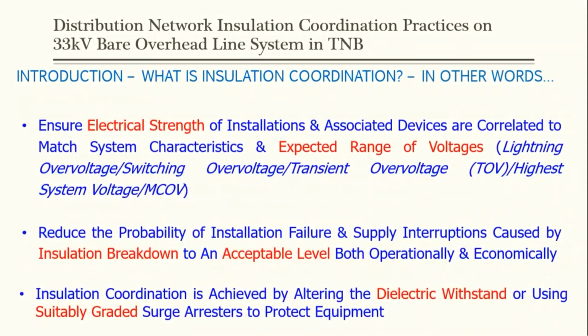So in other words, because we have a mouthful of definitions from IEEE and IEC, to put it simply, we want to ensure the electrical strength of insulations and associated devices are correlated to match system characteristics and the expected range of voltages. And what are the expected range of voltages? It can be lightning overvoltage, switching overvoltage, transient overvoltage or TOV, highest system voltage, and MCOV, or the maximum continuous operating voltage.